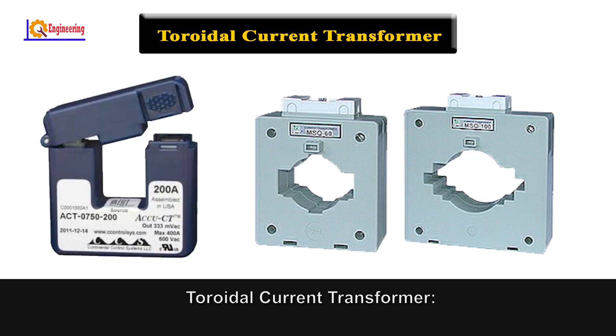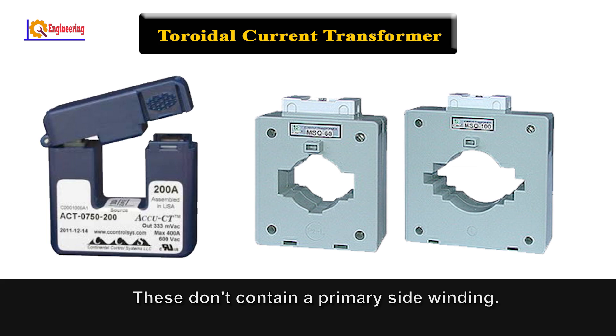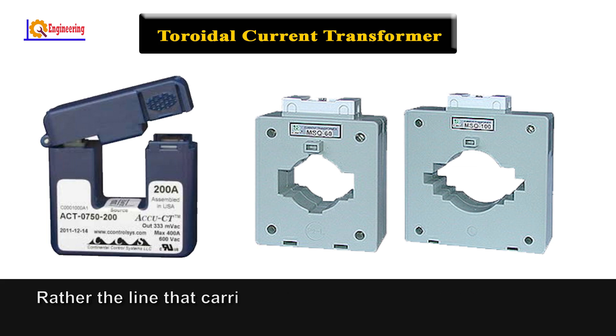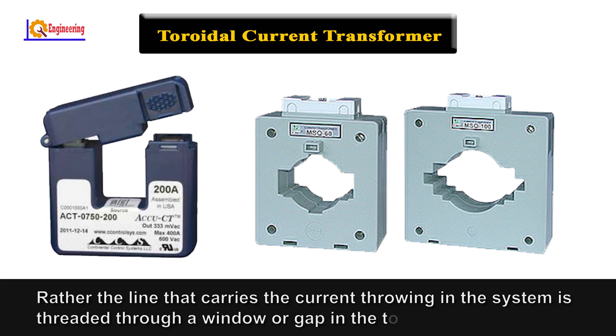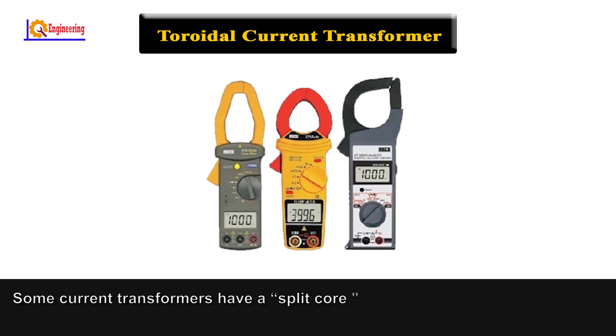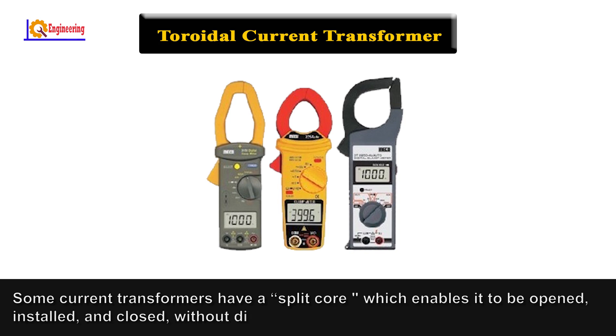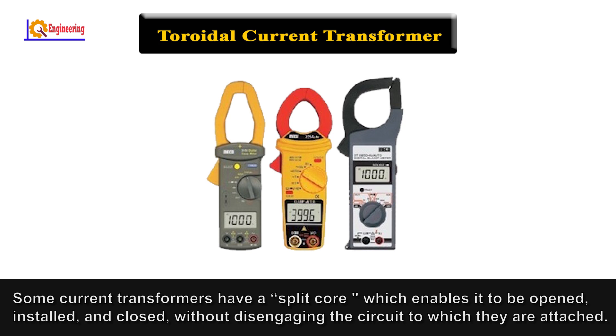Toroidal current transformer: This type does not contain a primary side winding. Rather, the line that carries the current in the system is threaded through a window or gap in the toroidal transformer. Some current transformers have a split core which enables them to be opened, installed, and closed without disengaging the circuit to which they are attached.